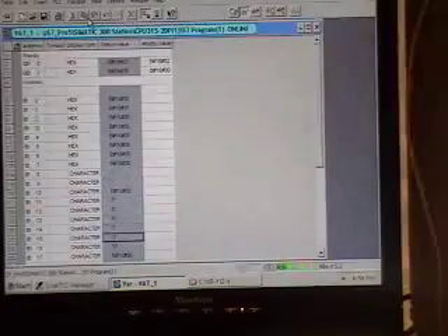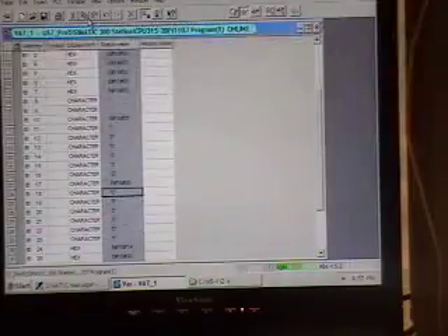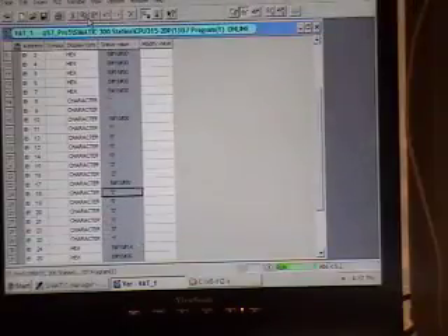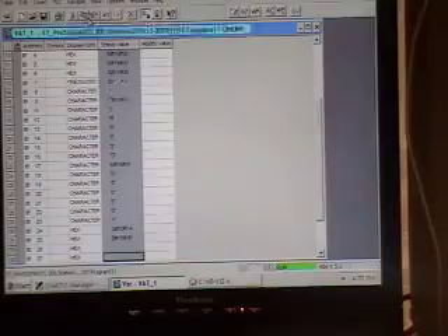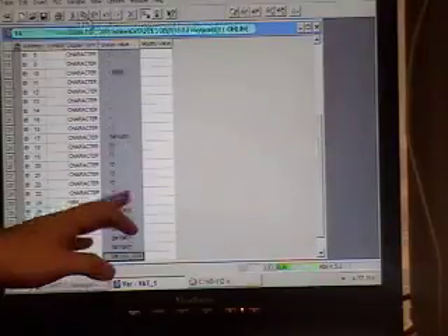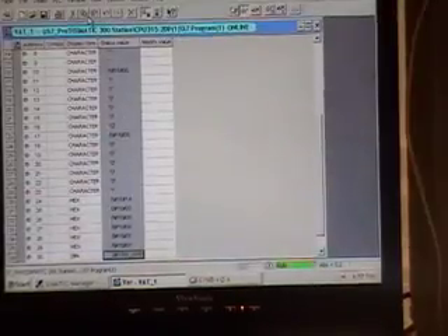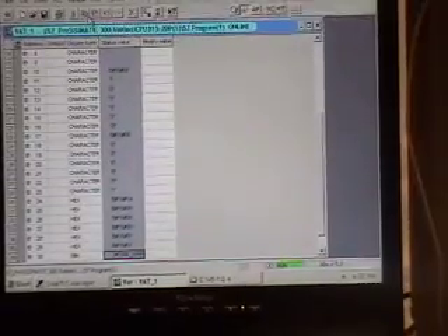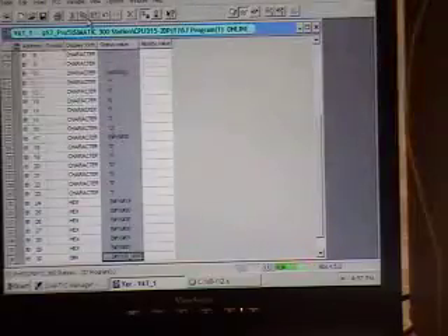If I move down a little bit, you can see that it's telling you the model number, 3000T. It knows what analyzer it is. We have a feature to put in a serial number of the analyzer so you can know what the serial number is. In this case, it's serial number 10000, but we can change the serial number of the analyzer. Encoded within these bytes over here, the last addresses, there are some troubleshooting bits that you can use to know whether the flow is okay, whether the pressure switches for the span gas and the zero gas are okay, and what valve is open. Because there is read back in this BB1, there is an input from the valve. So if the valve does not open, it will let you know. It's really checking that out. So if the valve fails, it will check it.